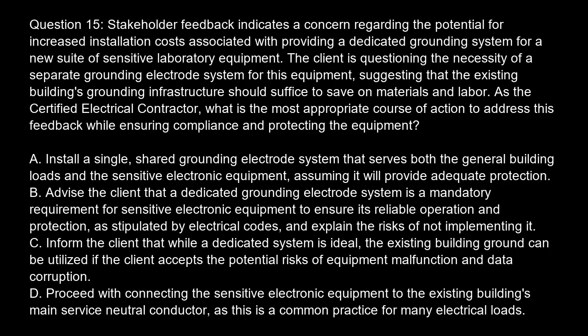Install a single shared grounding electrode system that serves both the general building loads and the sensitive electronic equipment, assuming it will provide adequate protection. Option B. Advise the client that a dedicated grounding electrode system is a mandatory requirement for sensitive electronic equipment to ensure its reliable operation and protection, as stipulated by electrical codes, and explain the risks of not implementing it. Option C. Inform the client that while a dedicated system is ideal, the existing building ground can be utilized if the client accepts the potential risks of equipment malfunction and data corruption. Option D. Proceed with connecting the sensitive electronic equipment to the existing building's main service neutral conductor, as this is a common practice for many electrical loads.